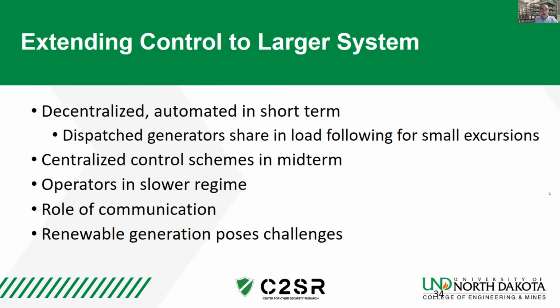Power system control, as you go to a larger system, has a very distributed feel. There are a lot of local autonomous controls that take input from a central control center. For very fast response, you use decentralized automated control. For slower response, you may have centralized autonomous control schemes, and then operators for even slower response. Part of the goal is to have operators do what people do best and not have them do things automation could do better. But you also need to look at the failure modes of that automation and the blind spots an operator has.